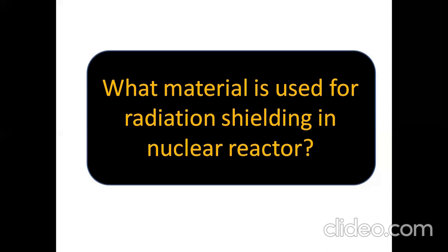The second material used for radiation shielding is concrete, with a density of 2.4 grams per centimeter cube. It is less efficient than lead but very easily available. The third material is steel, with a density of 7.8 grams per centimeter cube. Steel is not an efficient shielding material but has good structural properties and is sometimes used as an attenuating shield.